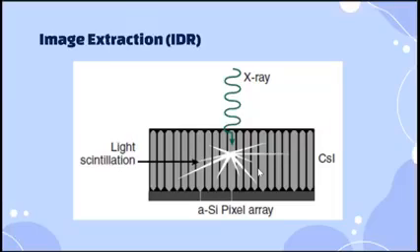Since light is normally emitted isotropically in all directions from a turbid or powder phosphor, which reduces image resolution, a method of forming vertical crystalline channels, such as this one, okay, in the cesium iodide layer or the gadolinium oxysulfide.